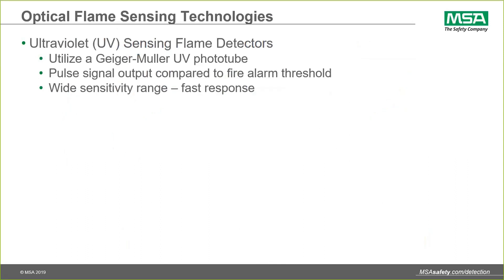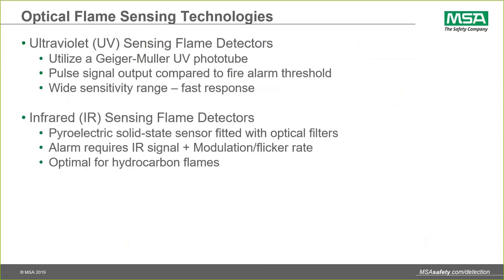Optical flame detectors started with ultraviolet sensing. These detectors use a Geiger-Müller UV phototube. They provide a pulse signal output in response to UV photons, and the signal processing around the UV detector compares that pulse train output level to a preset alarm threshold — traditionally 25 pulses per second. They bring a wide sensitivity range and very fast response, but unfortunately also had drawbacks, meaning they would respond to lightning and welding, which led to the development of a complementary optical sensing technology: infrared.